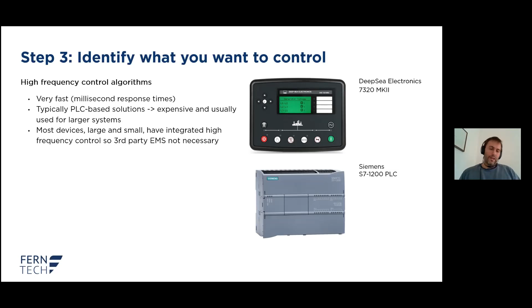At Ferntech we've implemented a list of control algorithms. The idea is to convert passive systems into closed-loop smart power systems. We have a growing portfolio of standardized algorithms - from automatically starting or stopping a diesel generator depending on the state of charge of the battery, to controlling a water pump as you can see here. That's a simple but useful example - turning a water pump on or off when the state of charge of the battery is very high. It's a good example of a deferrable load.